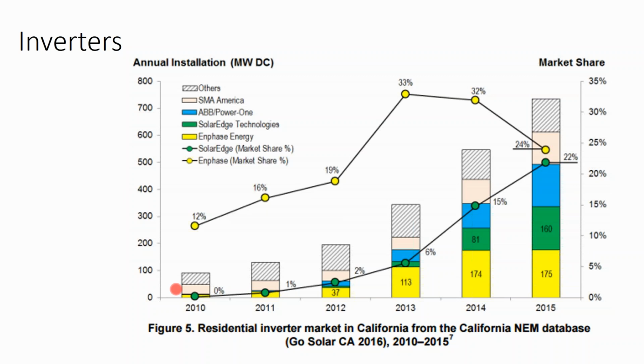I did a lot of solar arrays in Texas, very hot in Texas. It's crazy. You drive across the Texas border and your thermometer just climbs and climbs and climbs. They spin those little fans inside the inverter around and around, pretty much 8 hours a day, 11 and a half months out of the year. For that, I'd much rather have a passive cooling system that's not going to fail on me.